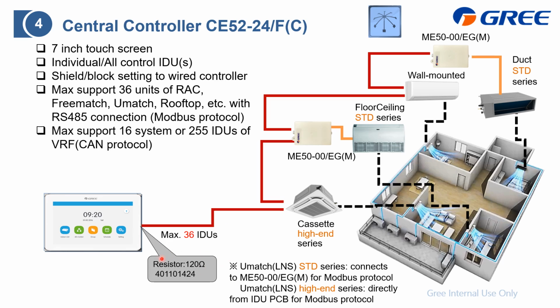And just don't forget the match resistor. Not only the UMatch, but also the FreeMatch, RAC, and rooftop can be connected on this bus. Besides, also the VRF, we can control from this central controller. And from here, we can individually control the indoor unit, or you can make a group control of the connected indoor units. And we offer you the shield and block setting from the wired controller, which is to block the setting from the wired controller, not allowed to set.